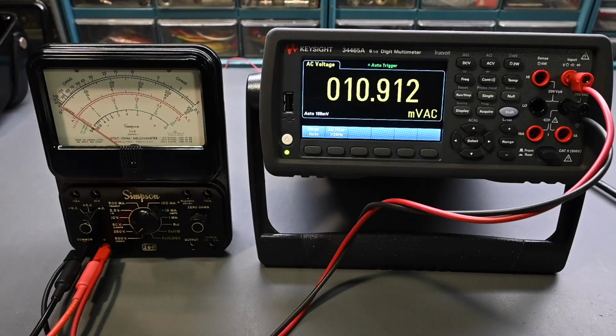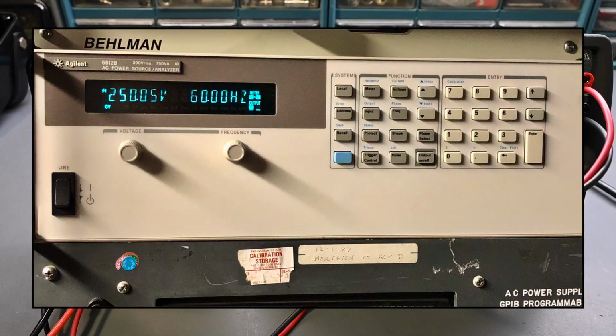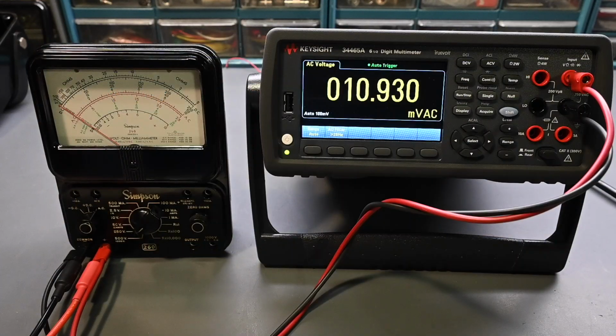Now for the 250 volts AC, I'm going to use my Agilent 6812B AC source. And I featured that in a repair video a while back, so if you're interested in seeing that, definitely check out that other video. Now the reason I'm using that AC source is because it provides an isolated output, which is important for safety. The same idea as using an isolation transformer. Of course, if you come across both AC lines at the same time, definitely a shock hazard, but it is isolated from ground. And also it provides a very clean and stable and regulated output, so it'll be a very stable AC voltage. If I use my isolation transformer and the variac to set the voltage, you know, there's line voltage fluctuations in the shop when devices are turning on and off, so it's nice to have that very stable output when you're doing a calibration like this.